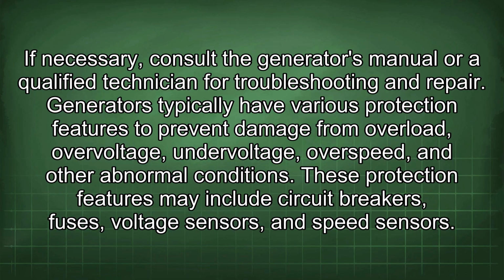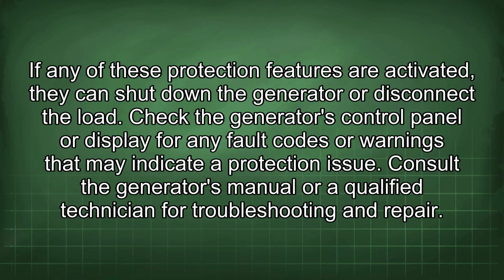Generators typically have various protection features to prevent damage from overload, overvoltage, undervoltage, overspeed, and other abnormal conditions. These protection features may include circuit breakers, fuses, voltage sensors, and speed sensors. If any of these protection features are activated, they can shut down the generator or disconnect the load. Check the generator's control panel or display for any fault codes or warnings that may indicate a protection issue. Consult the generator's manual or a qualified technician for troubleshooting and repair.